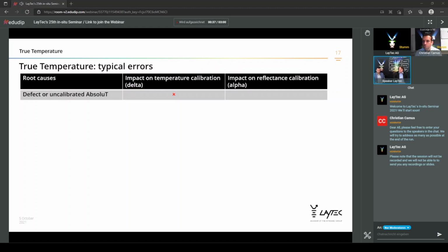So it's essentially important that you treat your absolute T carefully, always keep it in the safe container, and, more importantly, make sure that it's calibrated within the recommended calibration cycles as mentioned in the manual and in the paperwork of the absolute T. If you see a significant offset or inconsistency in the resulting delta or consistency of the true temperature when you do the true temperature or EpiTT calibration, even though the absolute T you are using was just recently calibrated or is even within the valid calibration period, then it's highly recommended to send it back to LayTec to have it inspected or maybe even repaired.